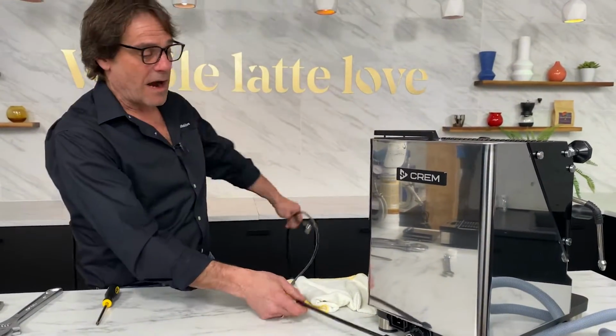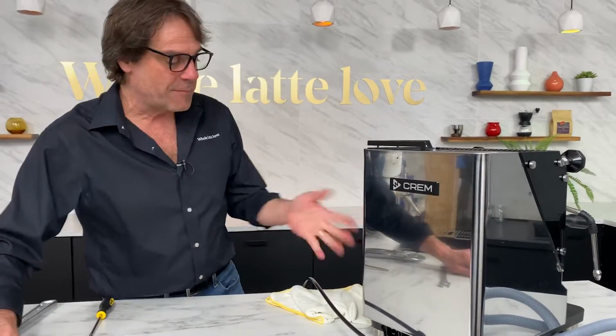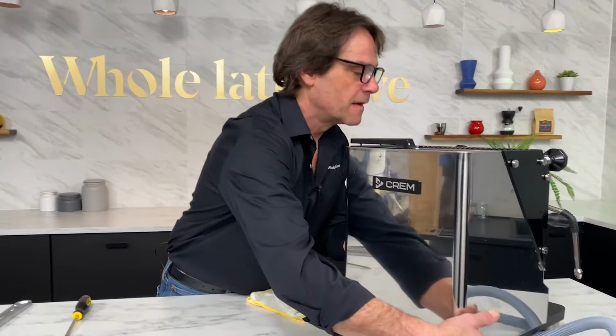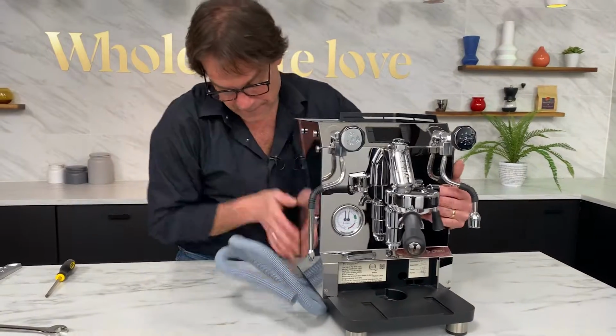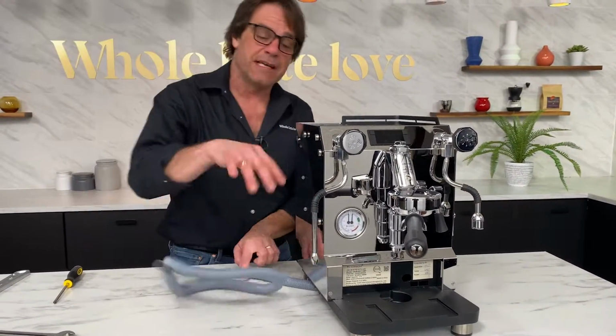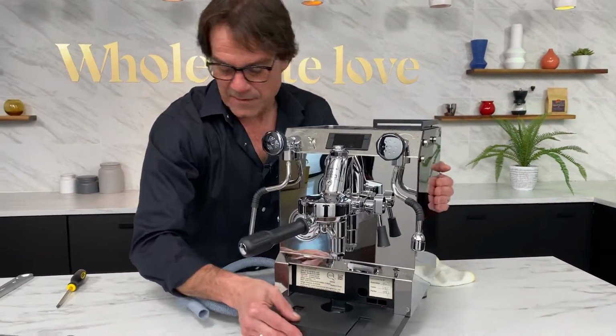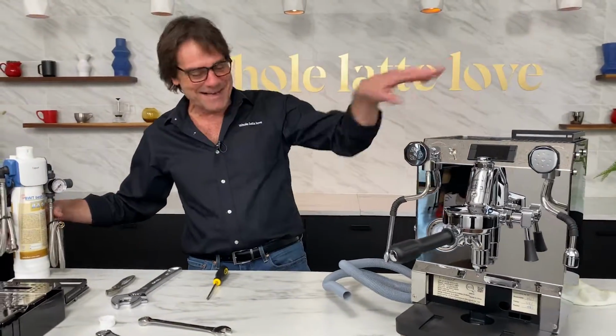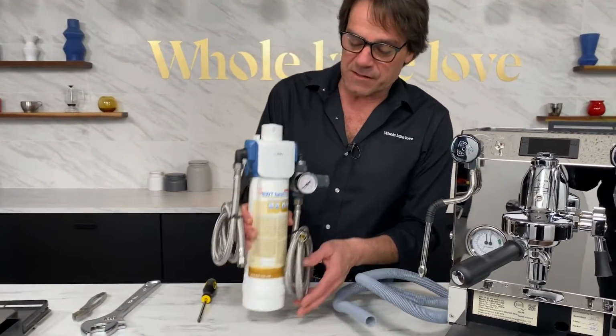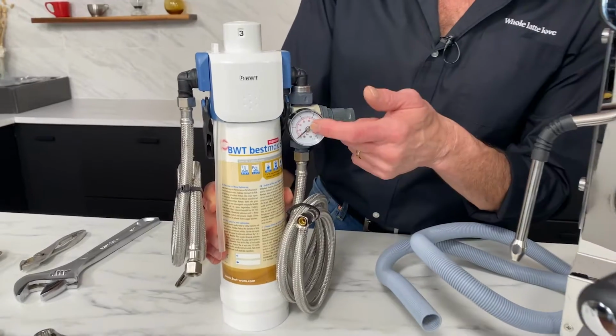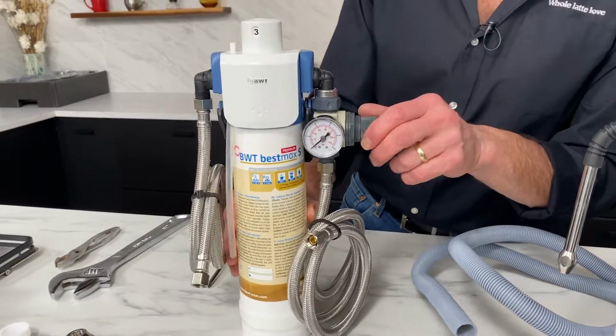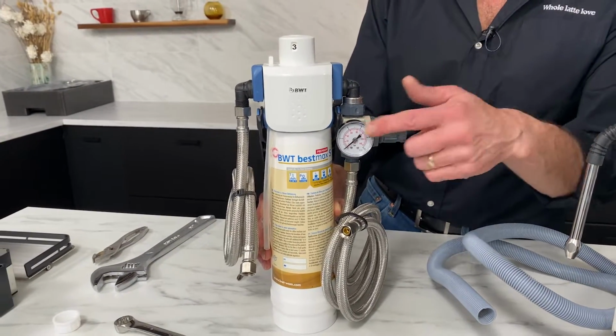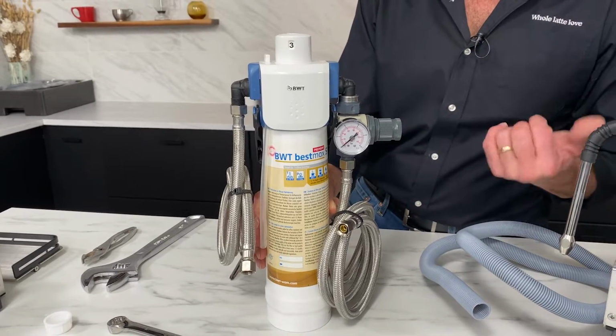So that's just running to our household plumbing. But let's talk about how we're getting water into this, because we really recommend that you decrease the line pressure. What we're using to feed this, under the sink over here, is this BWT Best Max Premium, and what we have here is a pressure regulator so we can adjust the pressure down. We like 2 bar of pressure minimum going into these machines.